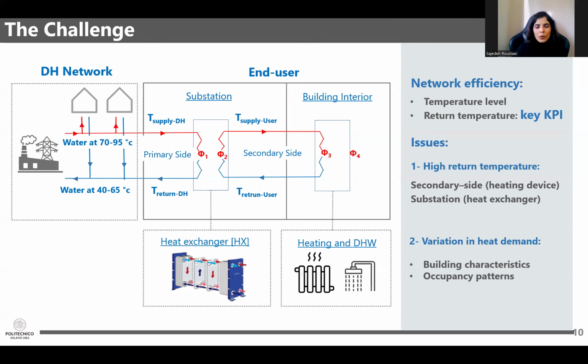This heat provides for the user's needs, and the cooled water returns back to the network. The temperature level on both supply and return lines is important, especially the return temperature, which is a key performance indicator since it shows how well the provided heat is extracted in different parts of the system. However, many existing networks struggle with high levels of this temperature.